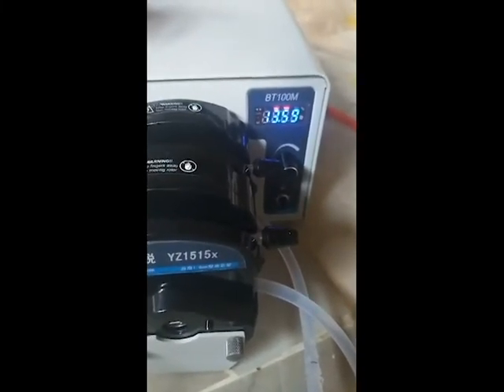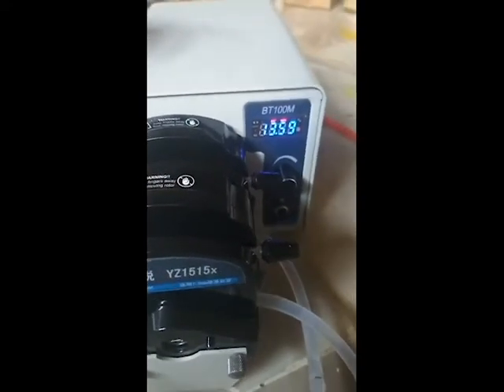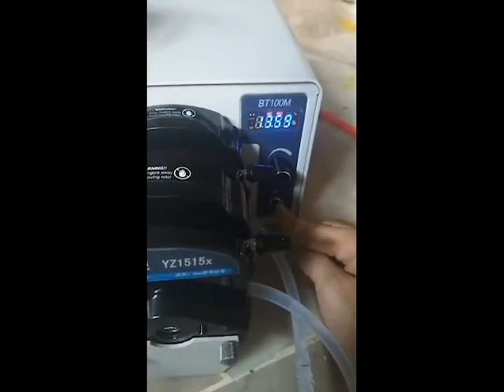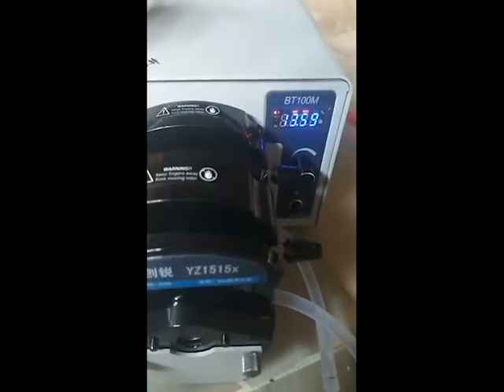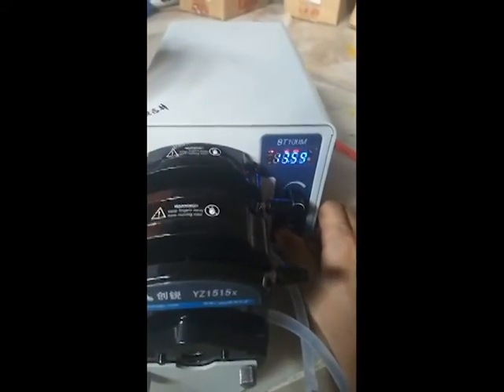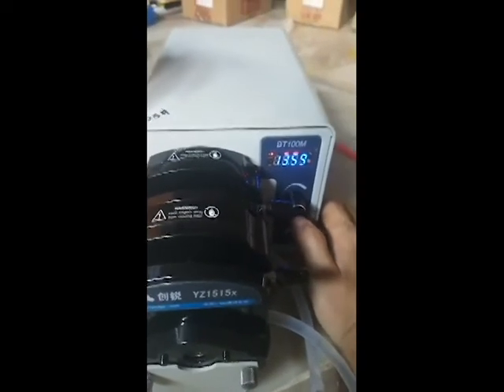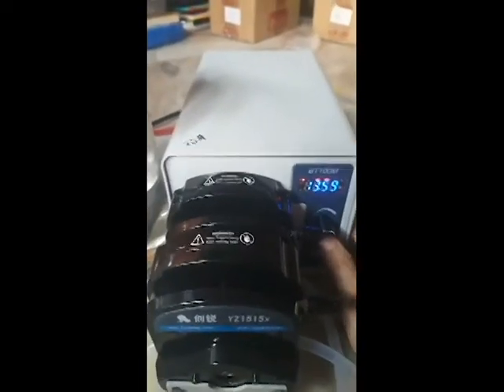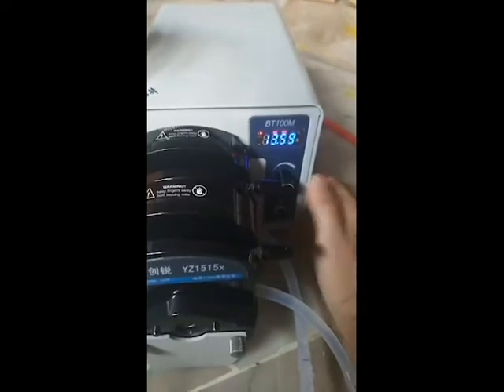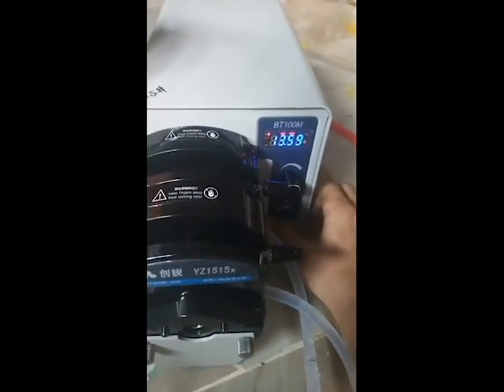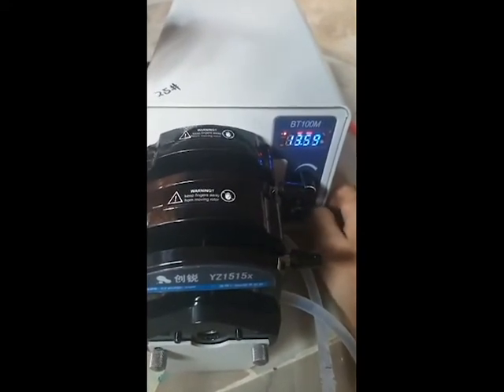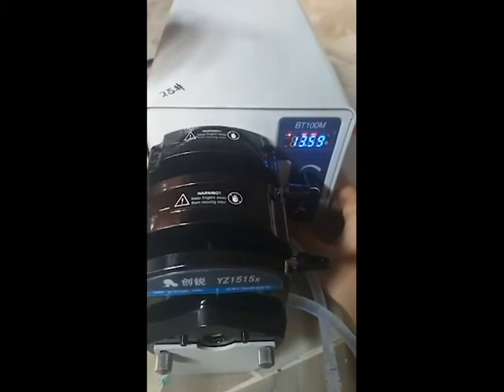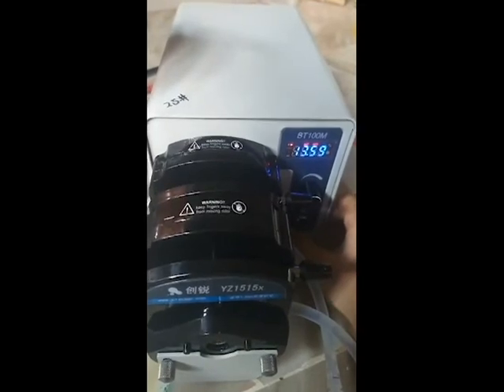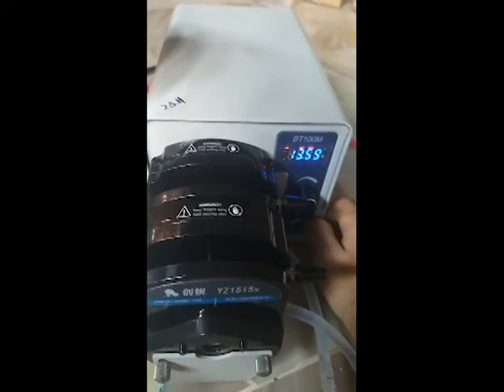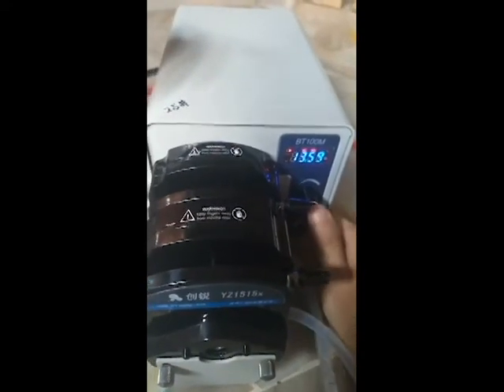And during the application, if you want the liquid to be reversed back to your reactor, you can let it rotate anti-clockwise. At this moment, it's anti-clockwise. It will reverse all the liquid back to your storage. And you can stop it. And if you want the liquid to be reversed or pumped somewhere faster, during the run status, you can click this button to let it run full. And this time, the liquid will reverse or charge into the system at very high speed, the maximum speed it will use. You will use this to ease your work when you plan to reverse all the liquid back to your storage, or when you need to clean the system or change the tube. Then you can do the full working.